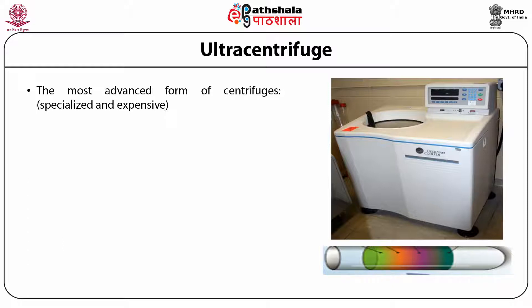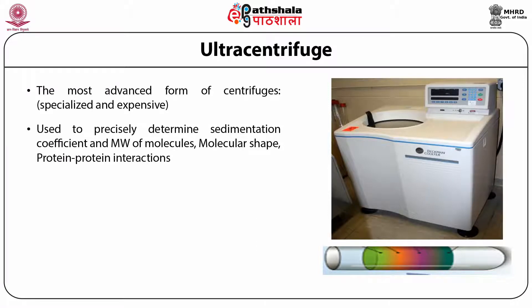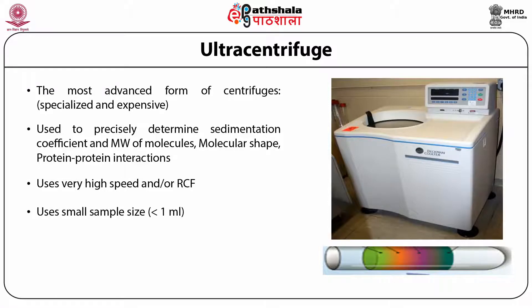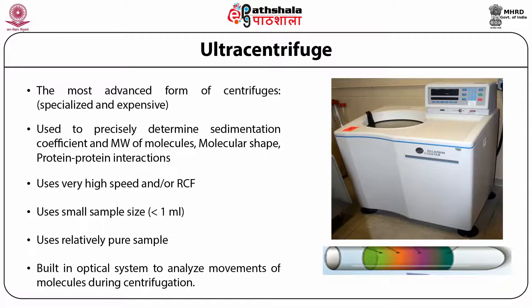Ultra centrifugation is the most advanced form. It is very specialized and highly expensive, used precisely to determine sedimentation coefficient, molecular weight, molecular shape, protein-protein interactions, and has a wide range of applications. It works at very high speed — more than 1 lakh RPM — and uses a small sample size, usually less than 1 ml, mostly for analytical purposes, although preparative forms also exist. The most advanced feature is its inbuilt optical system, allowing analysis of molecule movement during centrifugation for determining biological and physical properties.